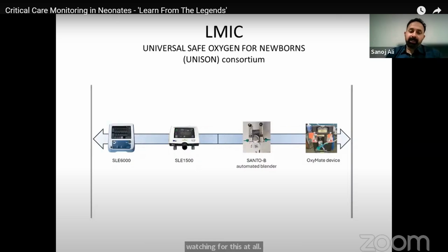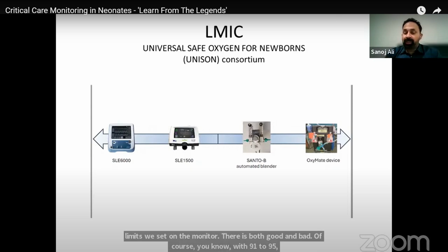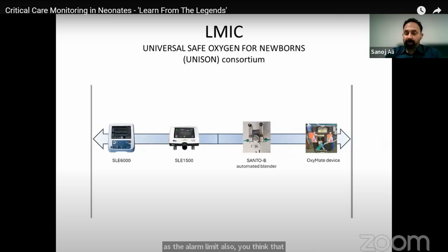The question on the alarm limits is, in our unit, we have 180 nurses and a 54-bedded NICU. Very difficult to be too complex about it. So we said, we're going to choose 91 to 95 as the SpO2 target for our unit. And we're going to use the same 91 to 95 as the alarm limits we set on the monitor. There is both good and bad. Of course, with 91 to 95 as the alarm limit, you think that you'll get tighter control and they'll be more proactive with it. But the corollary is that it'll lead to nursing alarm fatigue, especially if the baby is swinging a lot.